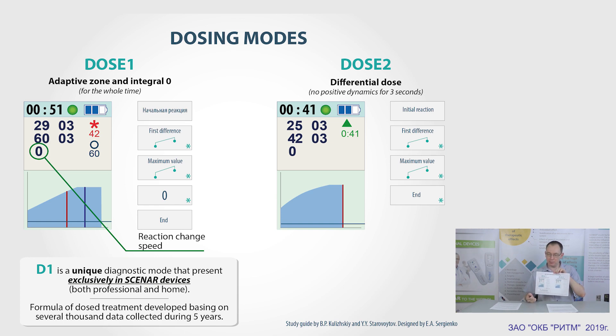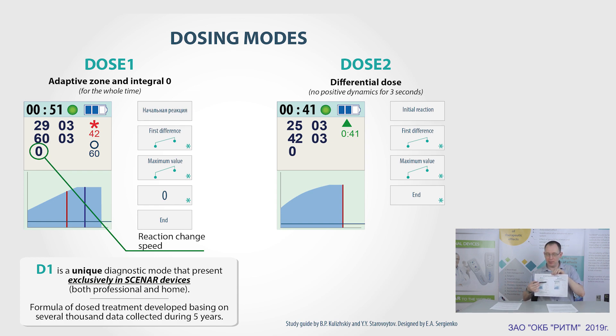Here is an example of working in D1 mode. The algorithm is built on binary comparison, which means that there is always a comparison of two parameters. First of all, we need to obtain the values of initial reaction of two points or places of electrode application. If there is no difference between them, just measure another point so that we have something to compare. We need to obtain a difference of 4 or higher. Then we can compare these two points and apply the electrode to the place with a higher value, holding it there until the dose signal.